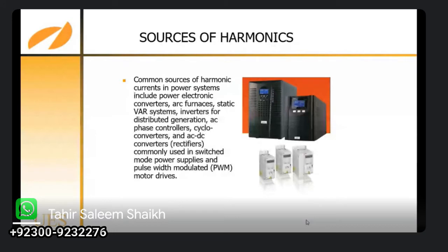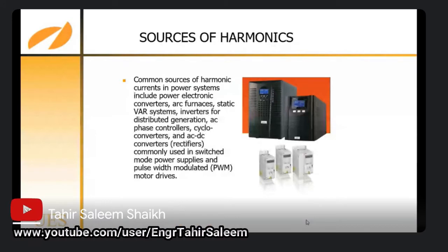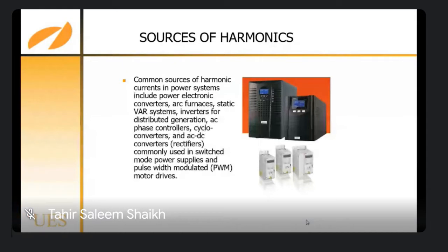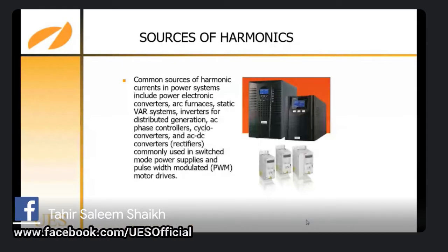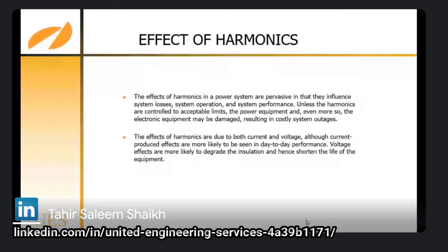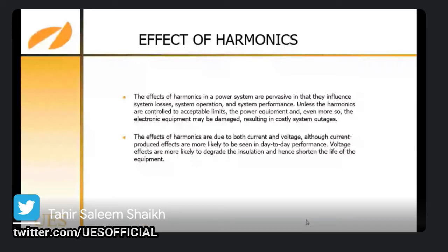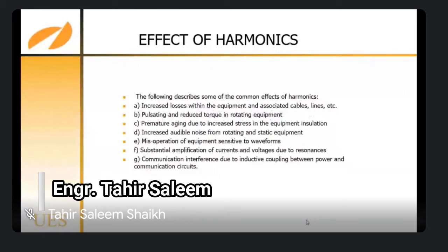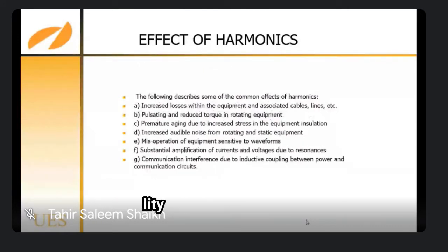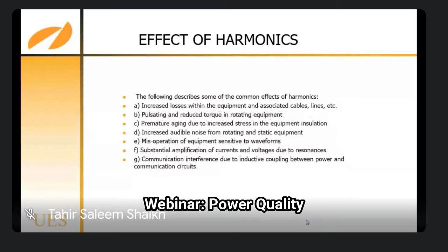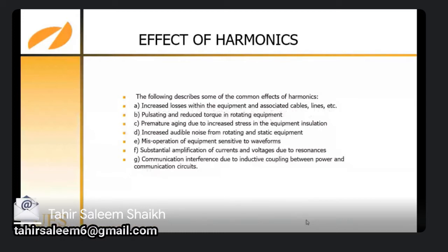The effects of harmonics are due to both current and voltage, although current-produced effects are more likely to be seen in day-to-day performance. Voltage effects are more likely to degrade the insulation and hence shorten the life of the equipment. That is a very important point. Now you can see over here common effects of the harmonics: increased losses within the equipment and associated cables, lines, cable losses increase, pulsating and reduced torque in rotating equipment. If you are using a VFD, this will give you a pulsating torque in rotation, and this will damage your bearings and so many things.